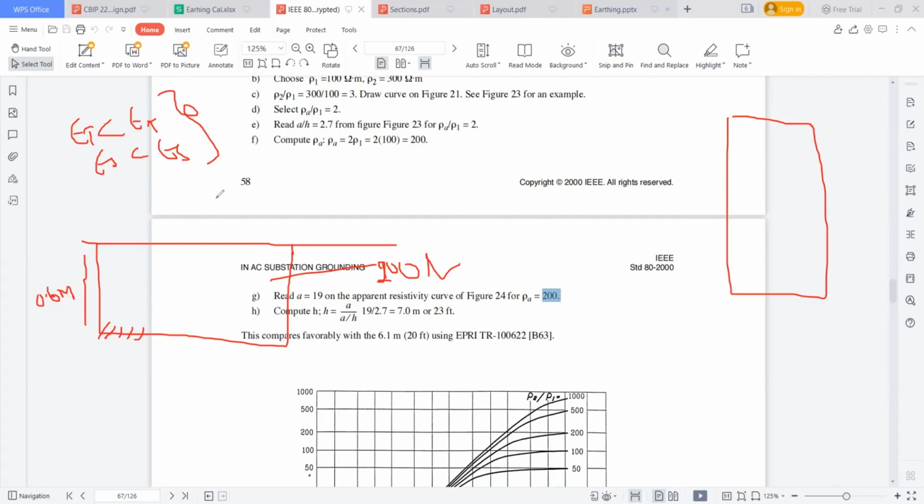So the last thing is, it's not attaining because of the high resistivity of the soil, which is the main effect on the resistance. So I have to decrease this resistance. So how can I decrease that? What I will do is I will remove the top layers of the soil, and I will replace this soil with some black cotton soil. Now this black cotton soil has a resistivity of, suppose, 100 ohms, right? Now, I can say that my resistivity of soil came to 100 ohms.